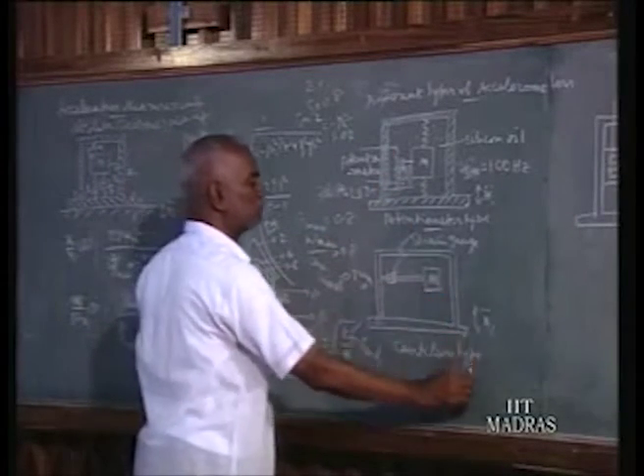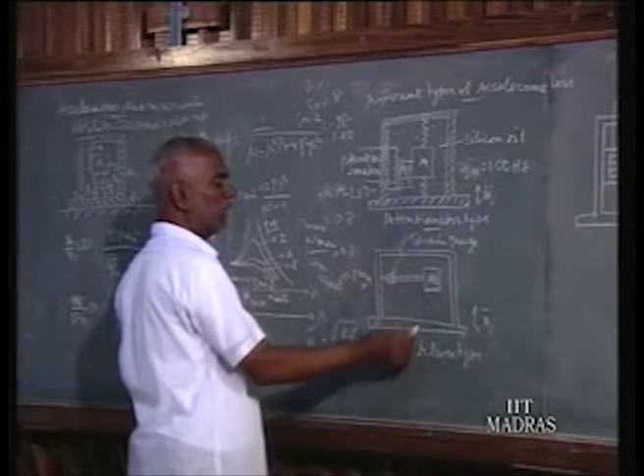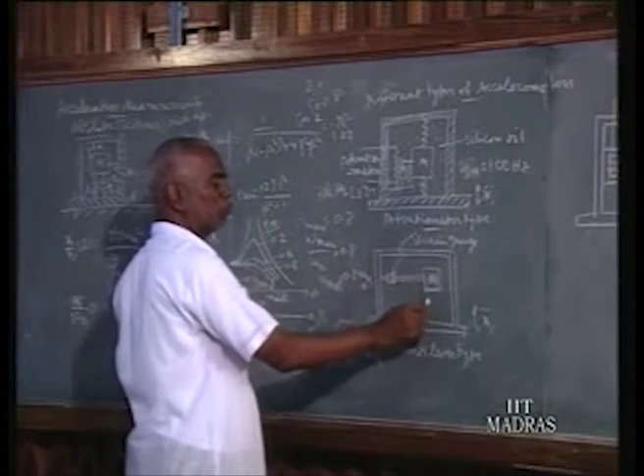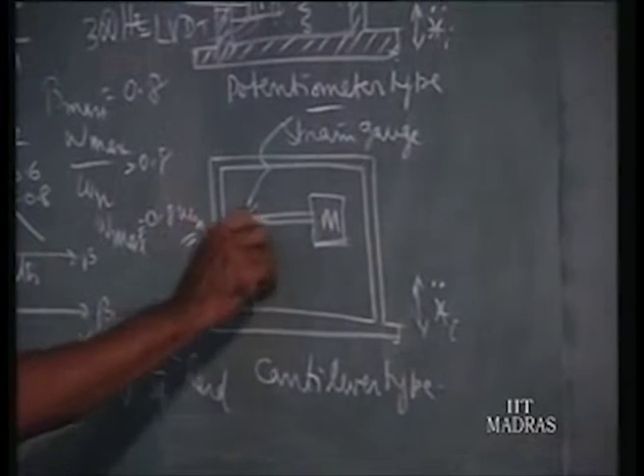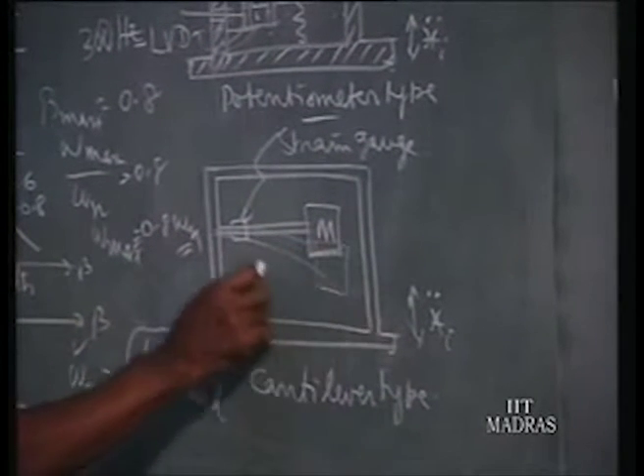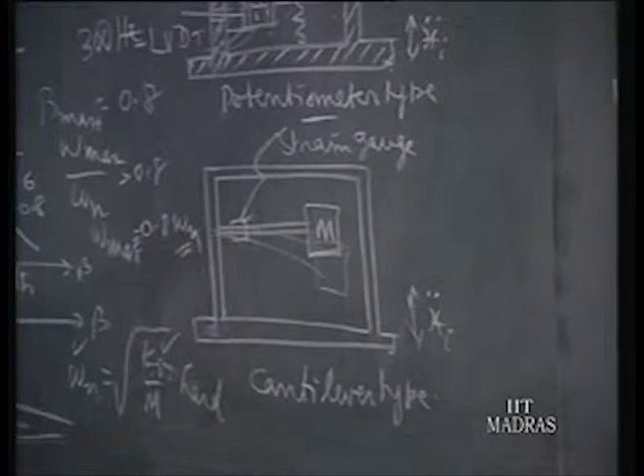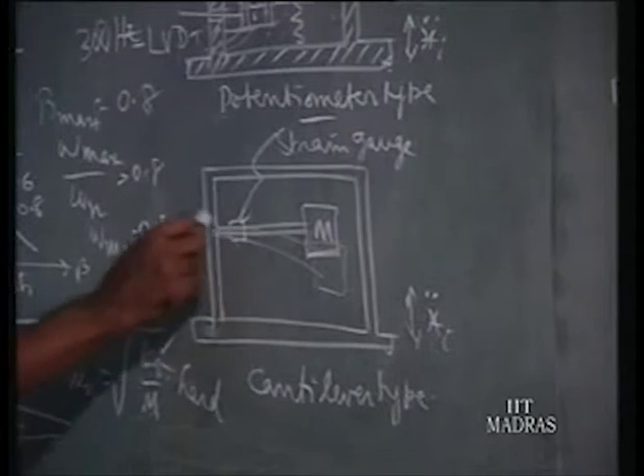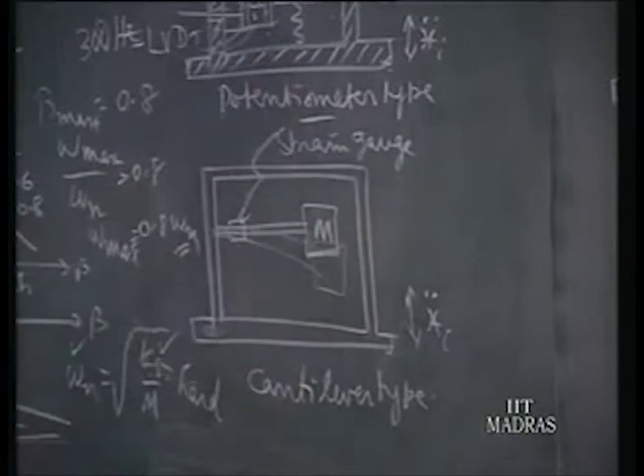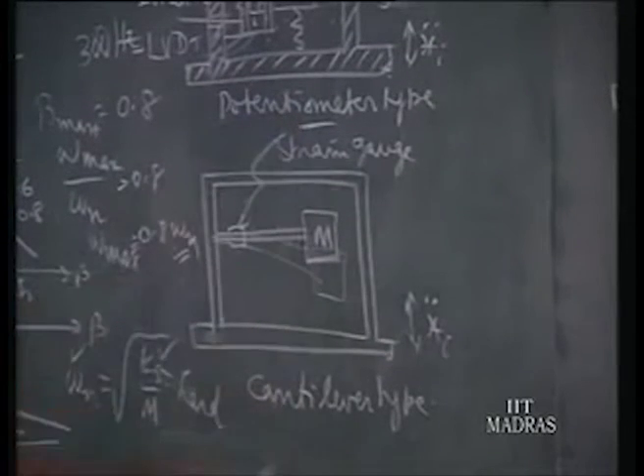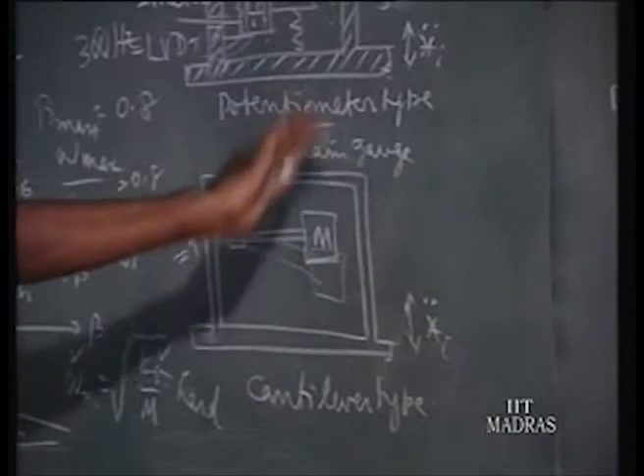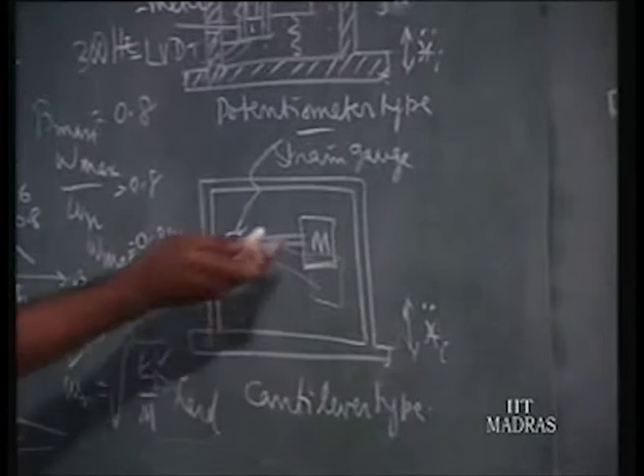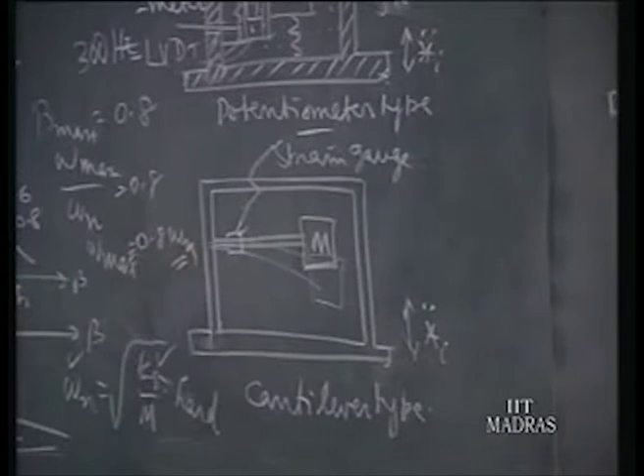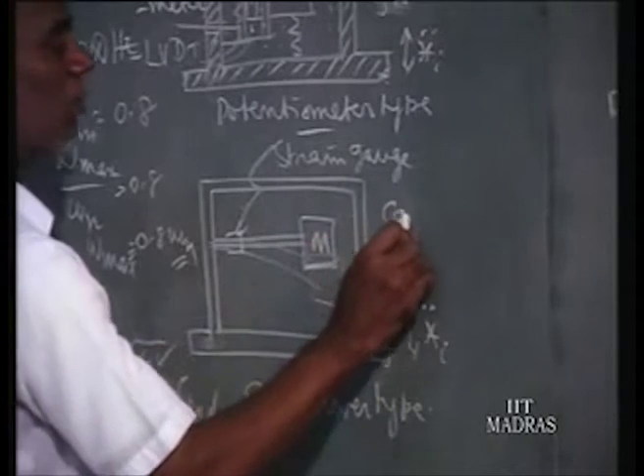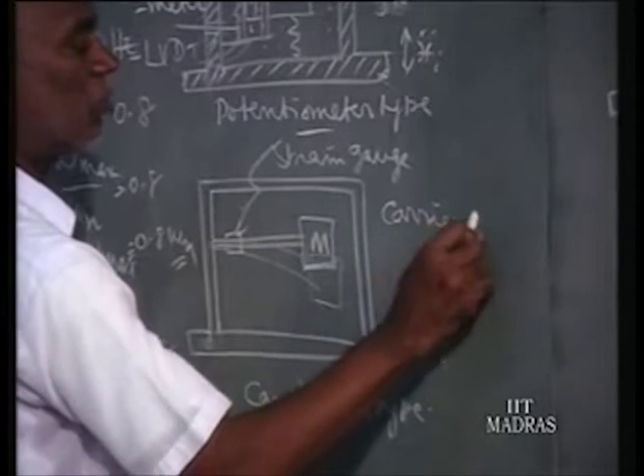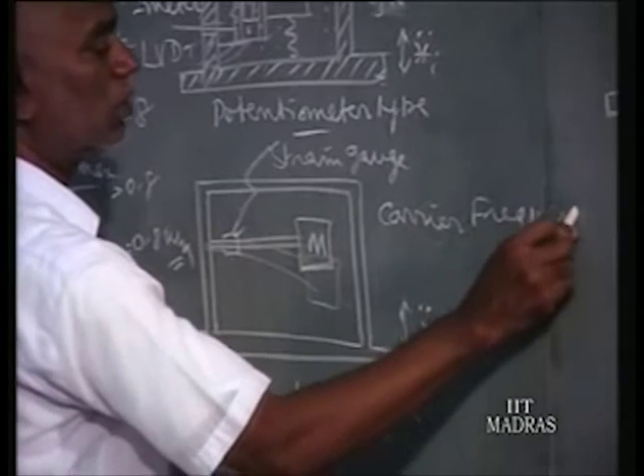So for this type, suppose it moves this way, due to inertia it tries to lag behind, so it bends. Due to the inertia force, when it is accelerated, it bends. When it bends, you will find stress and strain are produced near the fixed end of the cantilever, and that strain is converted into an electrical signal by using strain gauges. So the strain gauge bridge and all will be built, and you can use a carrier frequency amplifier, which you have learnt already.